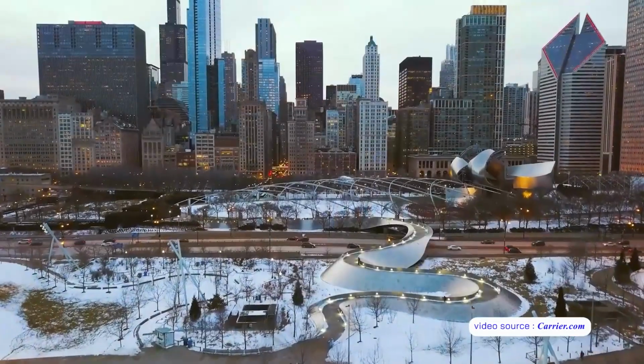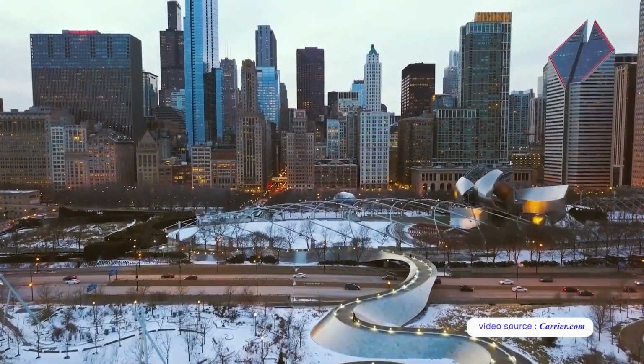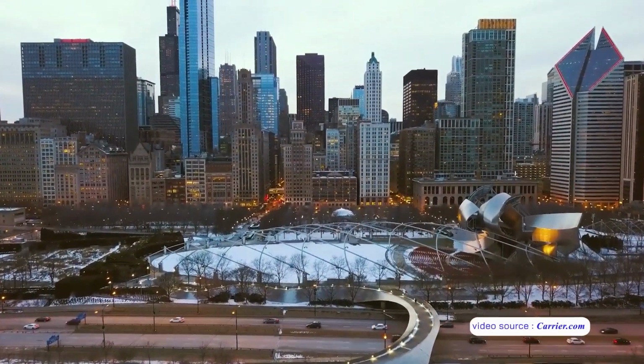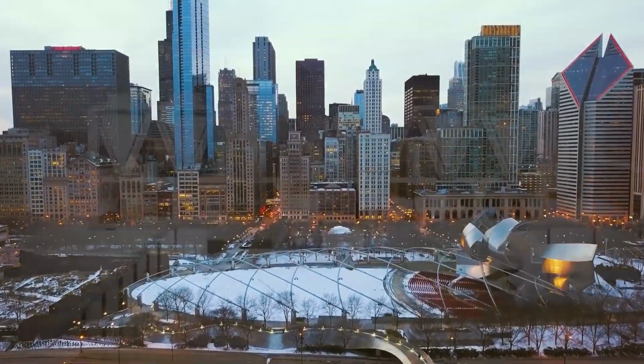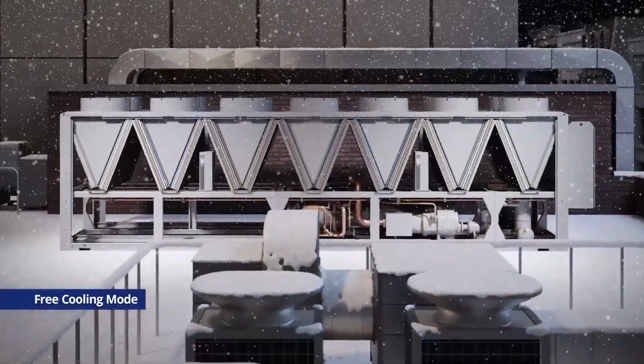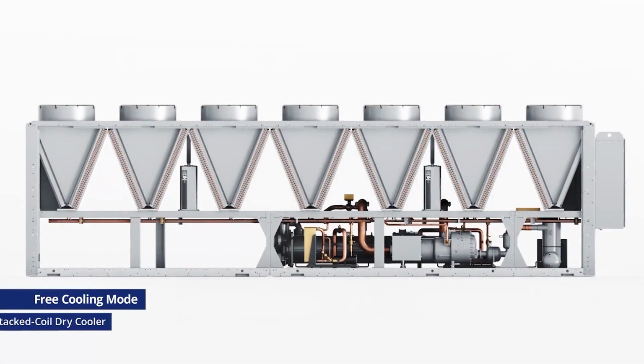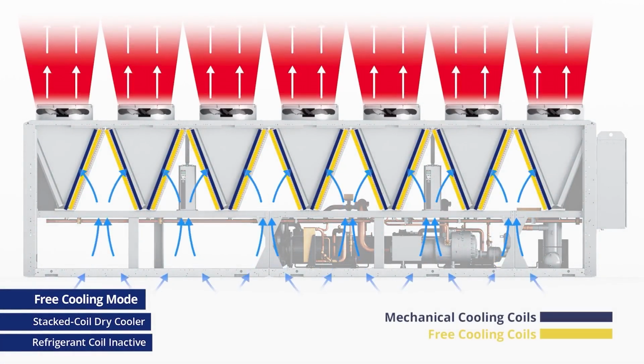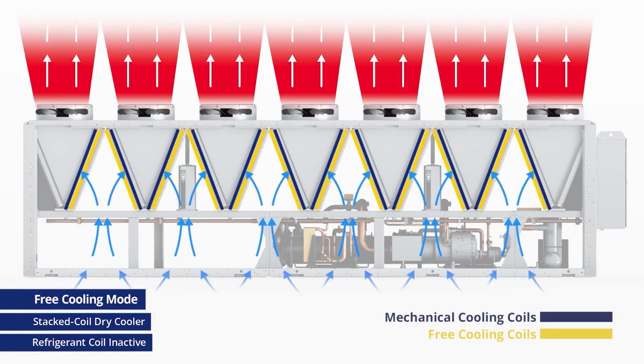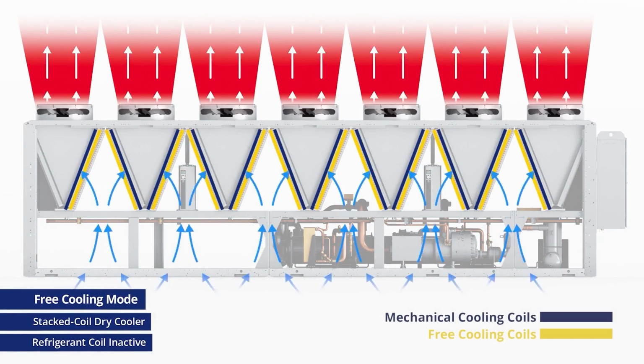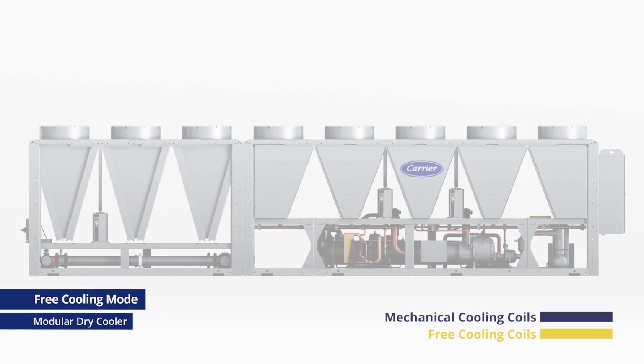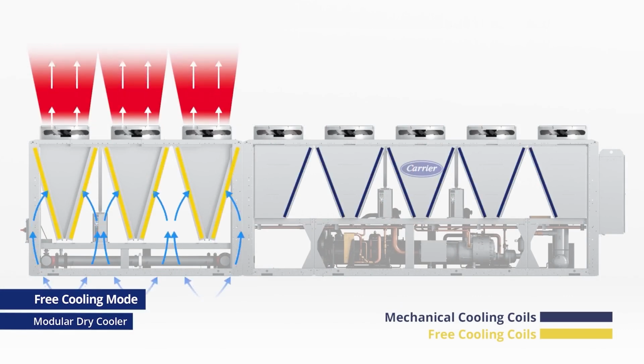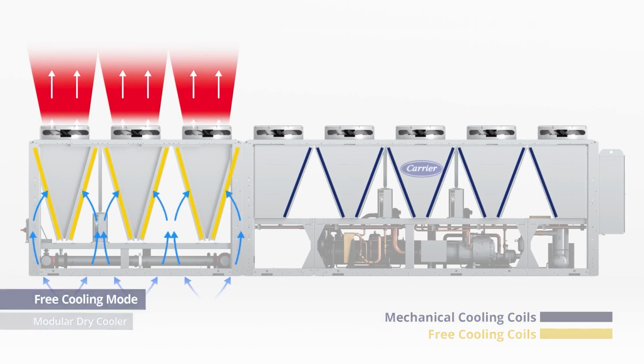When the ambient temperature is low enough, mechanical cooling can shut off completely, and the set point can be met by free cooling mode alone. With the stacked coil design, air again needs to flow over both sets of coils when only one is active, wasting energy. With the modular design, only the free cooling section will be active, maximizing free cooling, while the fans for mechanical cooling will turn off, once again saving energy.